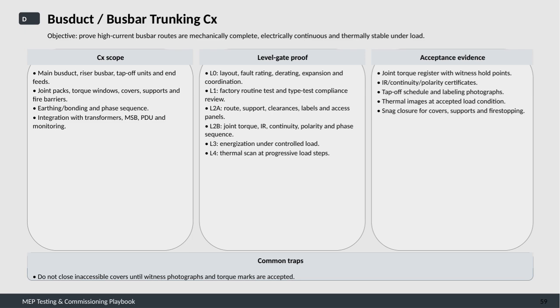For acceptance, we need documented evidence including joint torque registers with witness hold points, insulation resistance and continuity certificates, tap-off schedules with labeling photos, thermal images at accepted load, and closure of any snags related to covers, supports, and fire stopping. One common trap to avoid is closing covers that are inaccessible before obtaining witness photographs and confirming torque marks are acceptable. This ensures no issues are hidden and the installation can be confidently signed off.